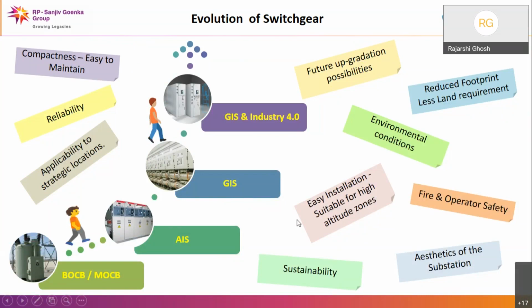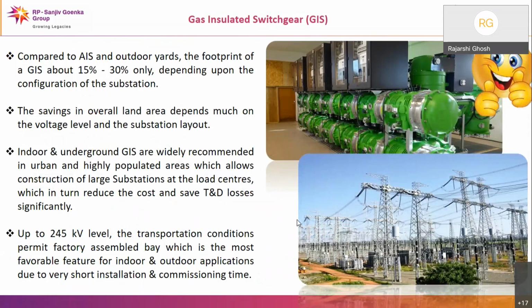So if we now go to the GIS, in the picture you can see this is a large outdoor yard with huge land requirement, and in urban areas land is like diamond. So there is a huge cost for this land, but you can see a large outdoor yard can be replaced with a small GIS board, which can be installed inside a room only. Compared to AIS and outdoor yards, the footprint of GIS is 15 to 30% only, depending upon the configuration. And as the voltage level increases, the space saving will be more. Indoor and underground GIS are widely recommended in urban and highly populated areas where the land requirement is less for the GIS.